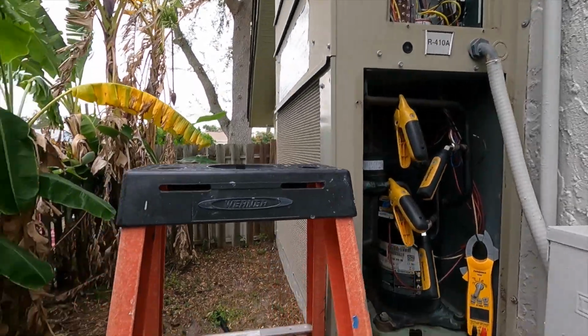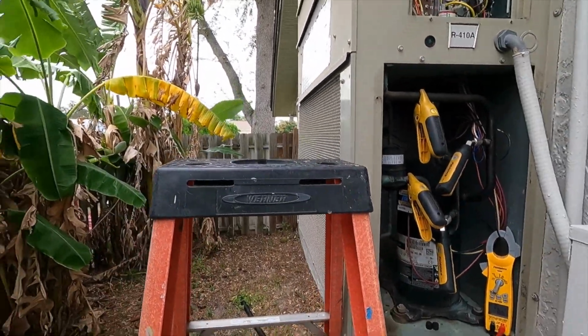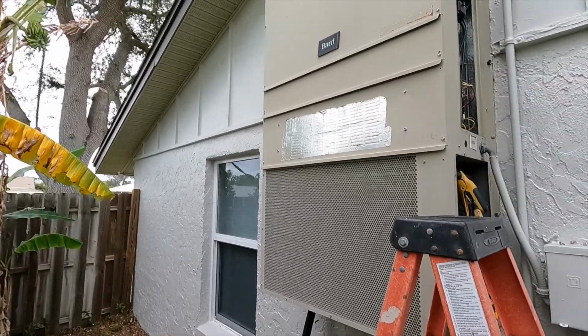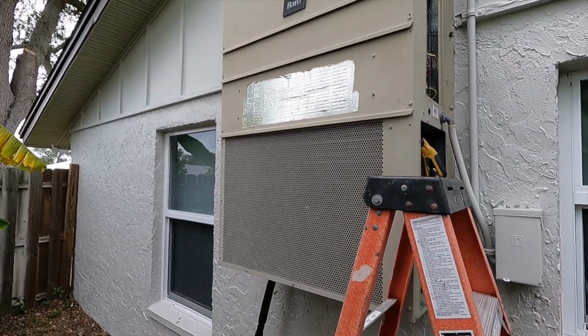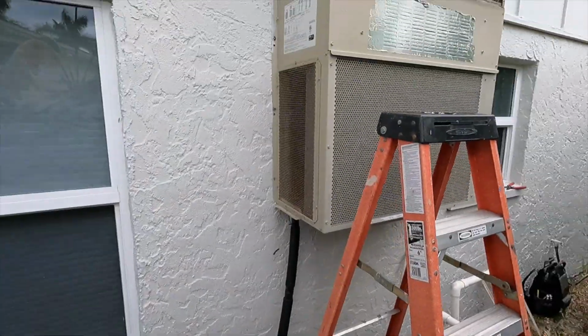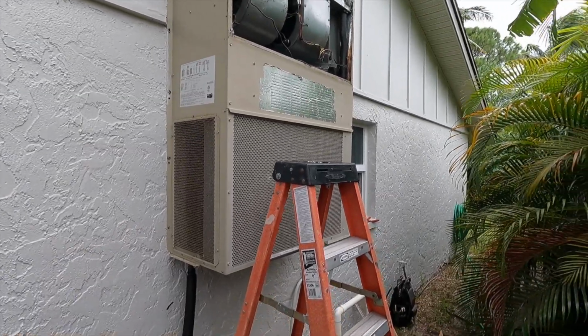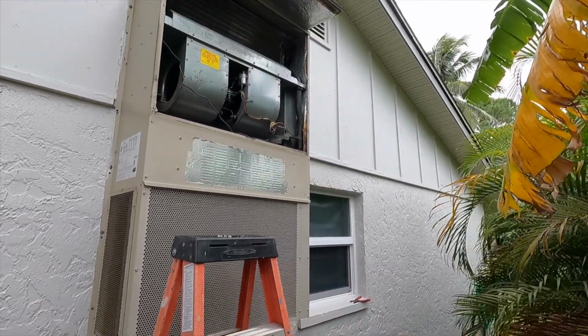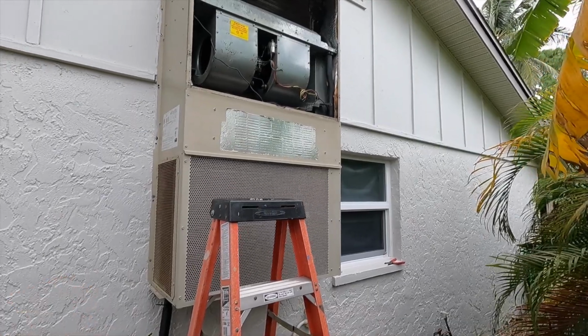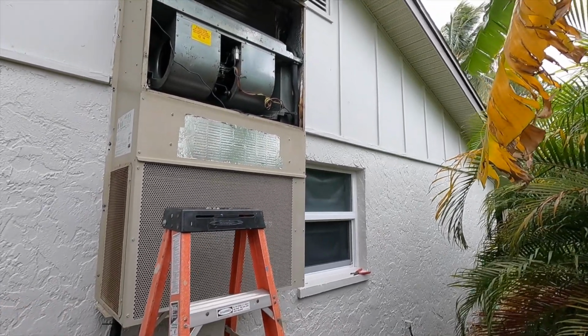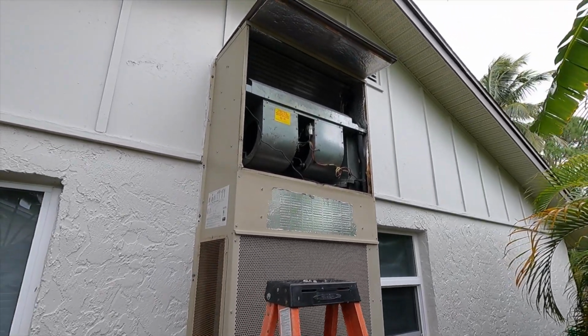So I'm going to go ahead and get the system off, get in position to clean everything. I'm going to remove some panels so I have better access to the equipment, and I'll check back in once we get there. All right, so the only panel I've not removed is the front grate for the condenser coil here. I'm going to be spraying that from the inside out, so I don't really need to necessarily remove that unless we have some chunky stuff coming out.